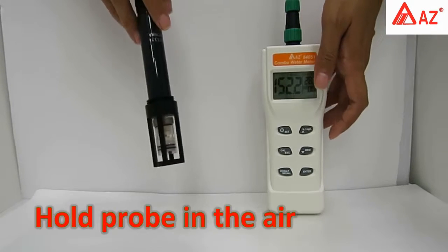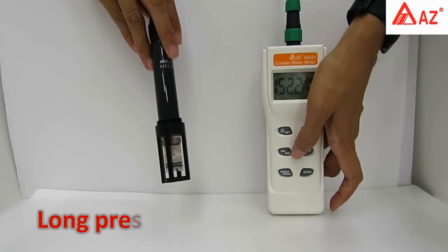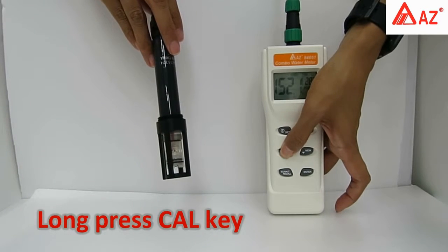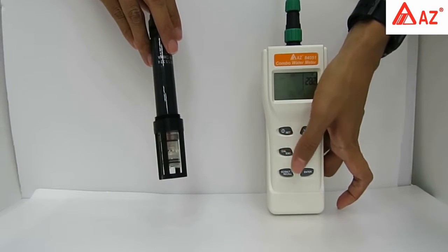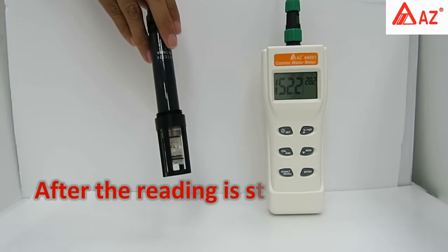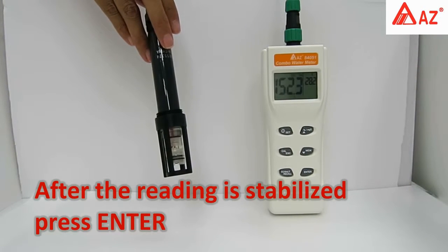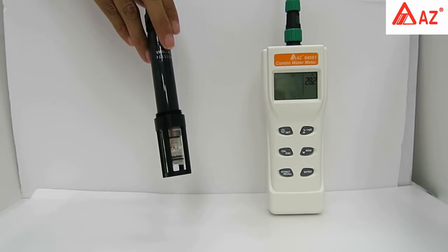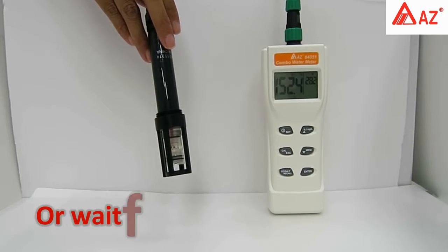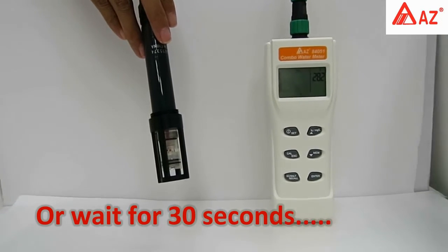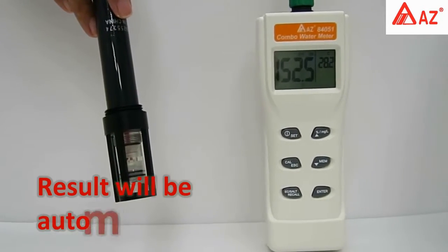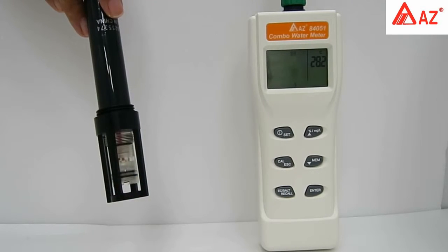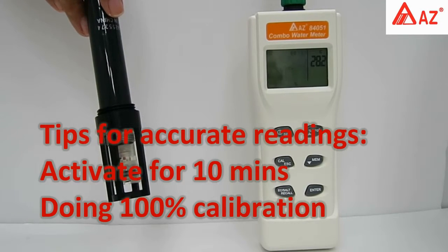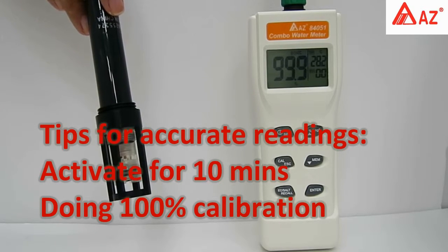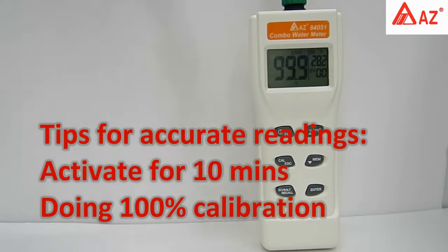Hold the DO probe in the air. Long press cal until the cal icon appears. After the reading is stabilized, press enter, or wait for about 30 seconds. SA appears when the result is automatically saved, and it will return to measuring mode. Remember to turn on the meter to activate the electrode for 10 minutes and perform a 100% calibration. In doing so, you can get accurate readings.